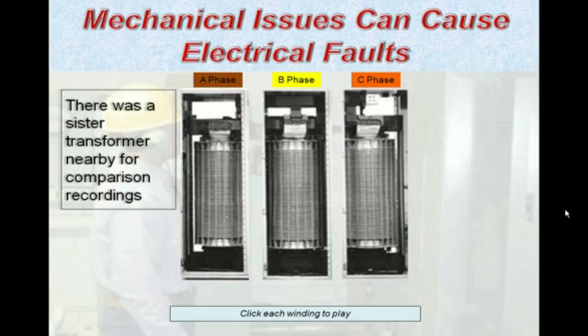Now, from a quality standpoint, it's very evident that there are differences aurally to these recordings, not just from an intensity or decibel level, but the quality of the sound. With transformers and magnetic lines of flux, there's inherently a 50 or 60 hertz emission that's created, but that particular recording had additional components superimposed on top of it that we'll talk about here shortly.